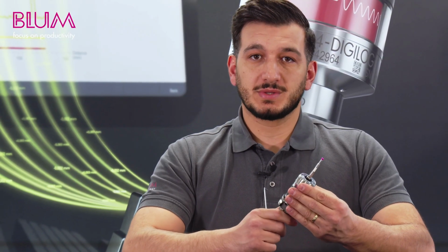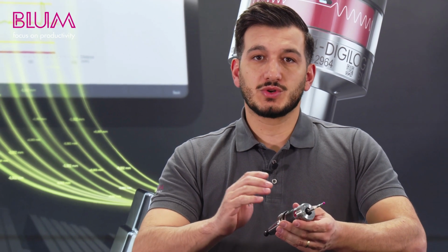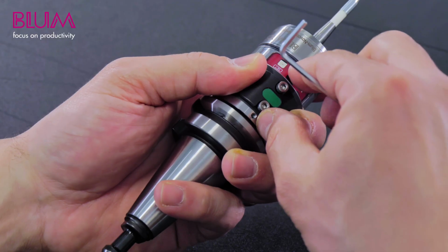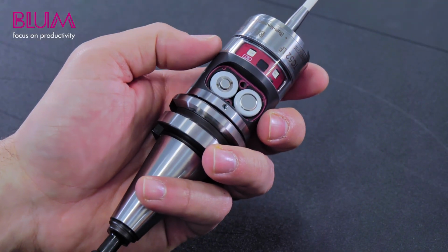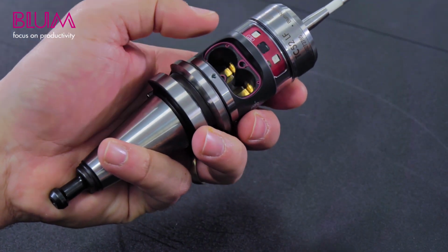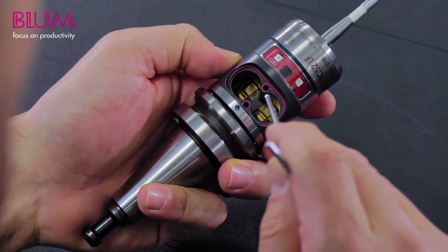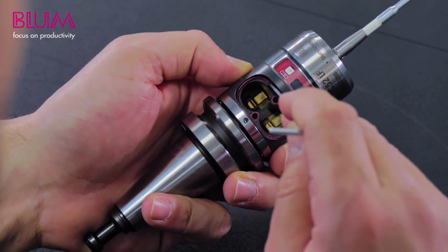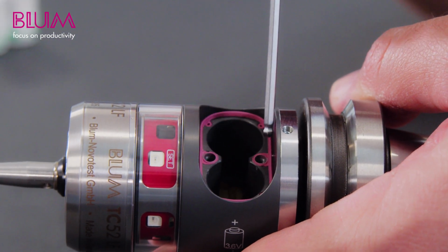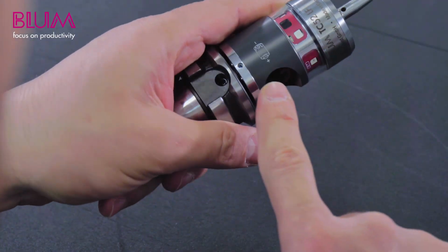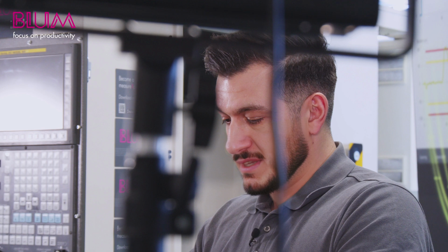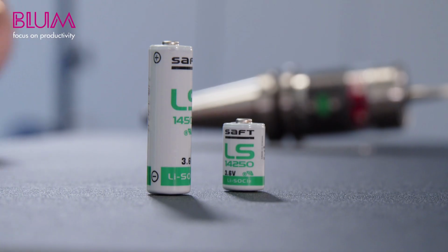Make sure that your probe is dry and clean beforehand so that no dirt gets inside as soon as we open the cover. Once the screws have been loosened, we are able to proceed with removing the battery cover and taking out the batteries. While you're at it, take a moment to conduct a brief visual inspection and a careful examination of the sealing ring and replace it with a new one if needed. You can clearly see on the side of the device how the new batteries are supposed to be correctly inserted into their respective slots.